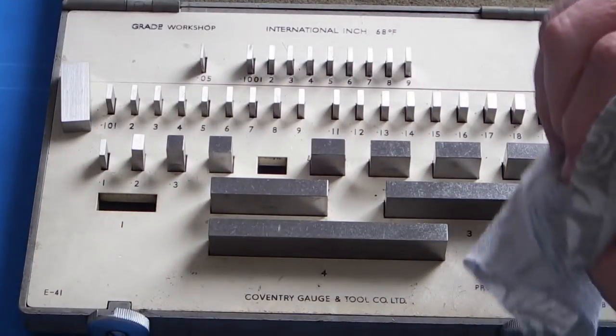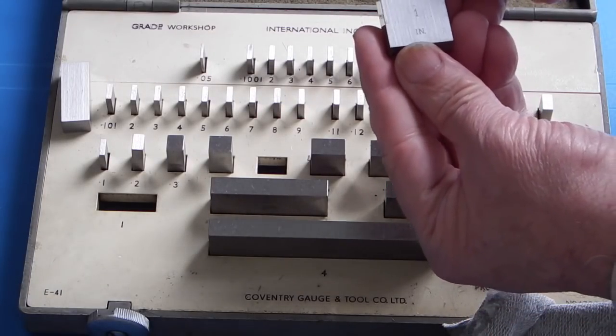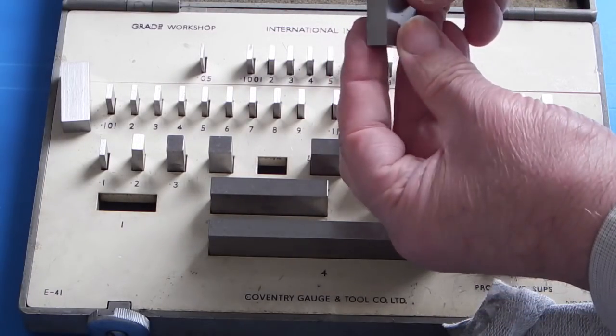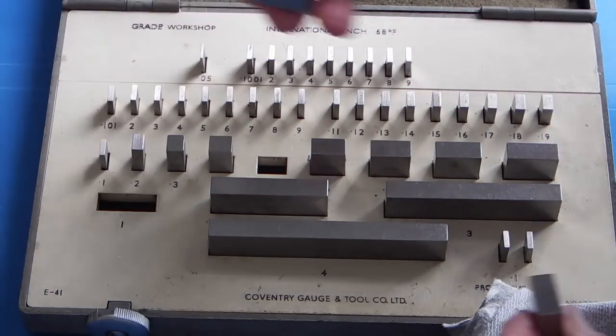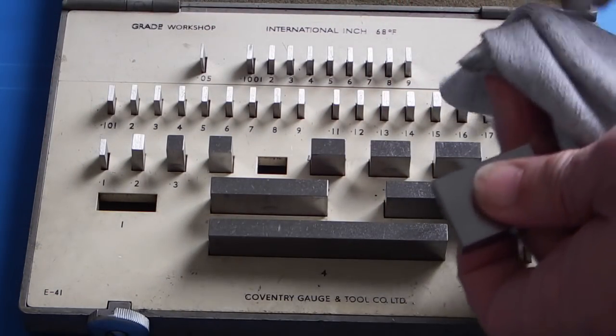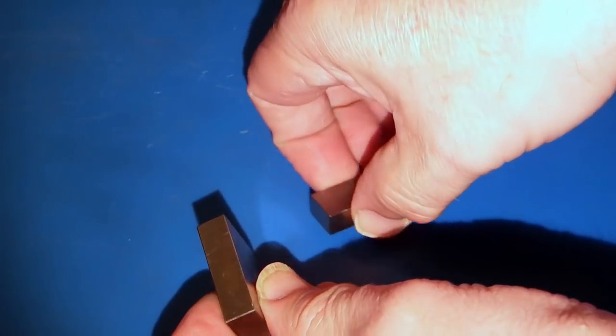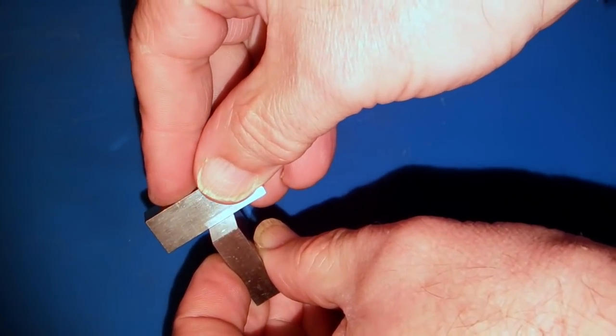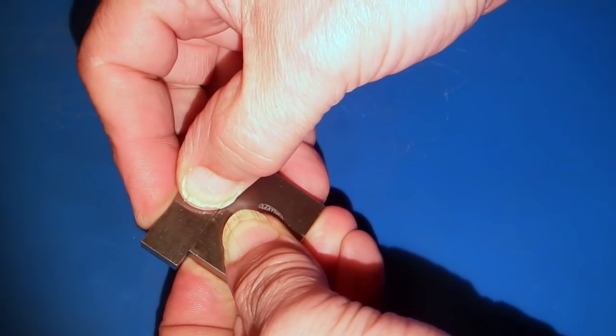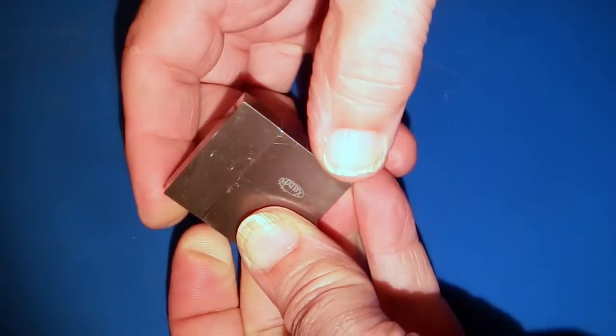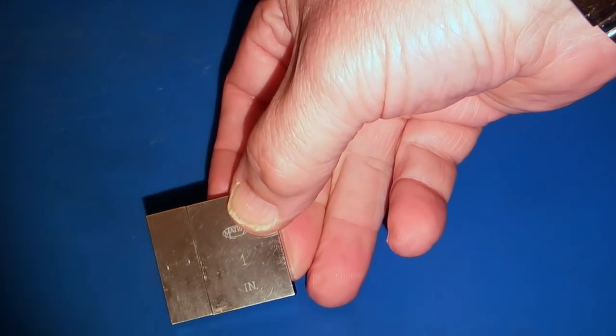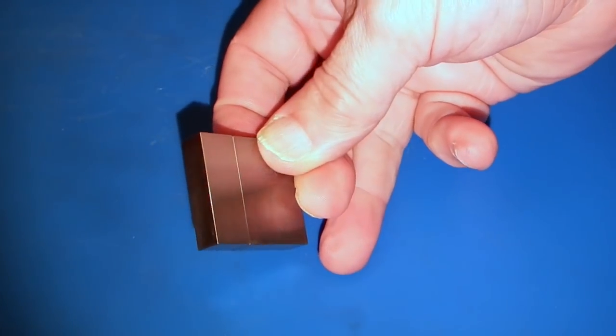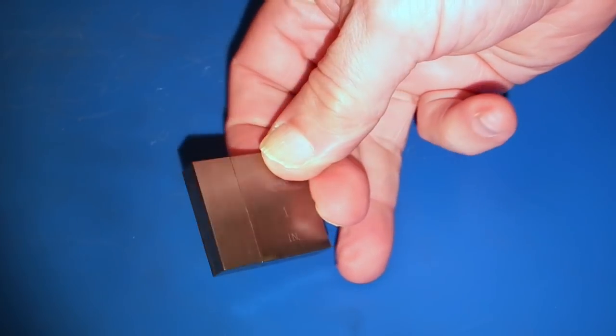If you look at a slip gauge or gauge block, it has on it a size. These are the faces that you use. You must clean the faces before you ring them together. The way you ring them together is put them 90 degrees, turn them together, move them in line, and that should hold. That will stay on there showing that it's been ringed correctly.